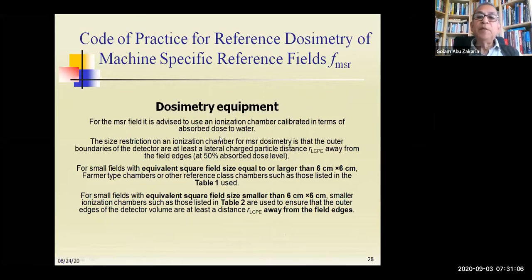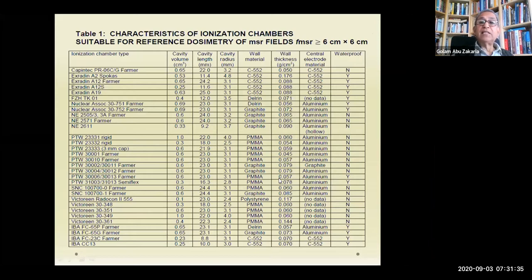So for the dosimetry equipment, it is important which chamber you select for the dosimetry for which field. Yeah, so in the TRS 483, they defined, to measure the machine specific field msr, two types of field: greater than 6 by 6 and less than 6 by 6. So there are two tables, and you see here the next. These are the characteristics of ionization chambers suitable for reference dosimetry of msr fields greater than 6 by 6. That means it is actually a conventional linear accelerator. So you know all this here, the rigid chamber and so on.